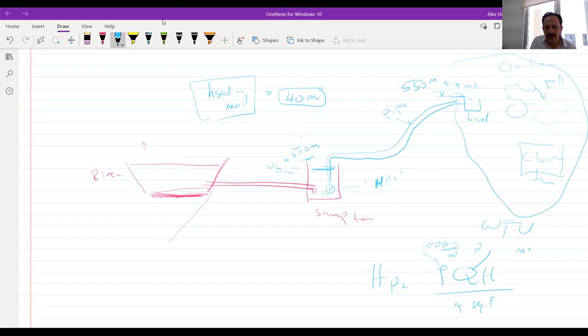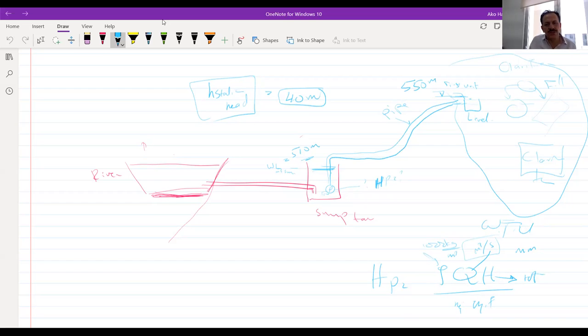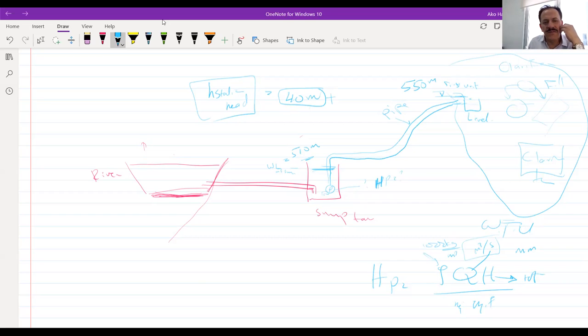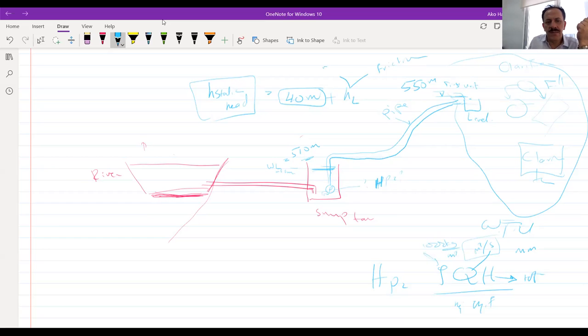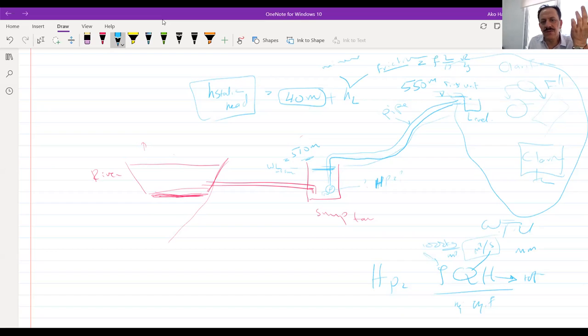Head losses consist of friction head loss and minor head loss. Friction head loss is due to pipe length: f·(L/D)·(V²/2g) — the Darcy-Weisbach equation. We have Q, pipe diameter, and pipe length, so we can find the velocity and calculate friction head loss. Minor head losses for valves, entrances, reducers, etc. are taken as 10–20 percent of the friction losses — you don't need to calculate each K value separately.